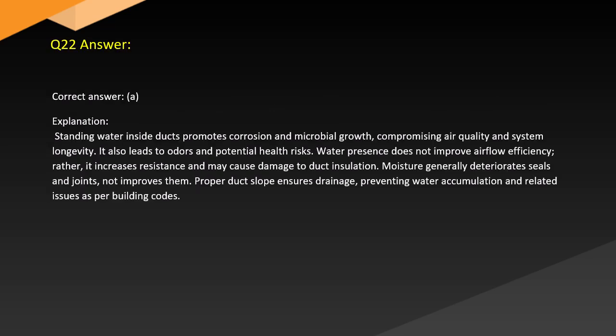Answer. Correct answer, A. Explanation. Standing water inside ducts promotes corrosion and microbial growth, compromising air quality and system longevity. It also leads to odors and potential health risks. Water presence does not improve airflow efficiency. Rather, it increases resistance and may cause damage to duct insulation. Moisture generally deteriorates seals and joints, not improves them. Proper duct slope ensures drainage, preventing water accumulation and related issues as per building codes.